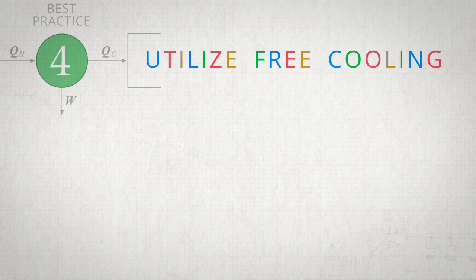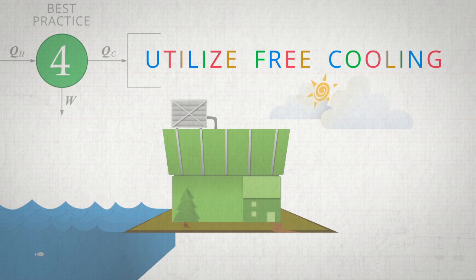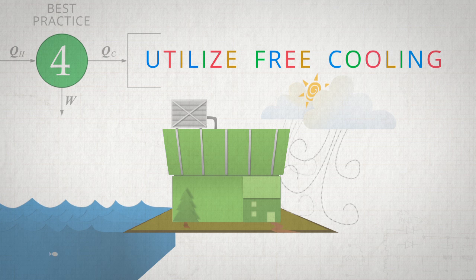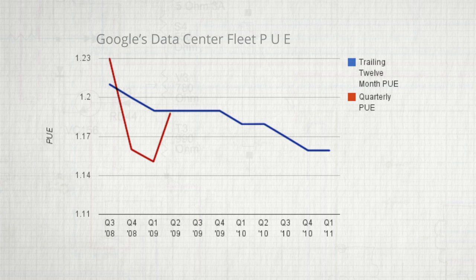Whenever possible, we recommend people to free cool. Free cool means utilizing ambient temperatures outside of your data center to be able to provide cooling without operating very heavy energy consuming equipment like chillers. We use free cooling at all of our data centers. And you can see this in our publicly reported PUE data, where the PUE values go up in the summertime and down in the wintertime. This is just a reality of running our operations with free cooling, and it yields tremendous efficiency gains.